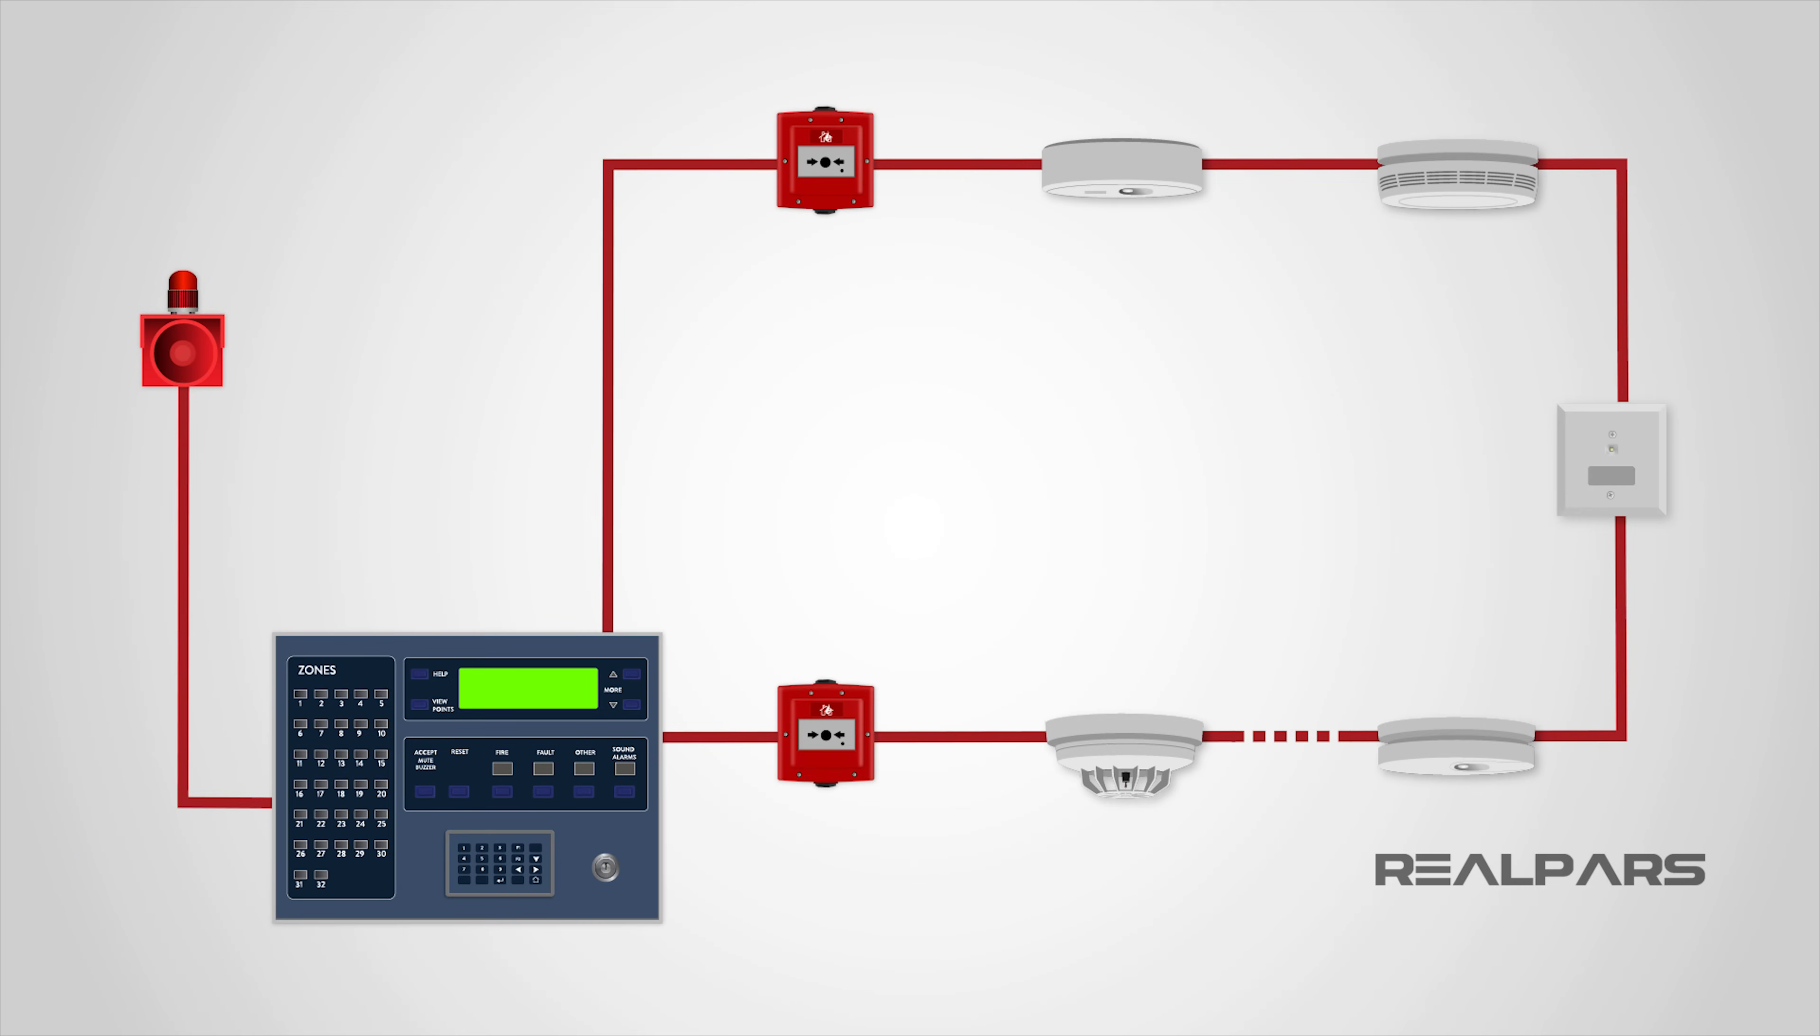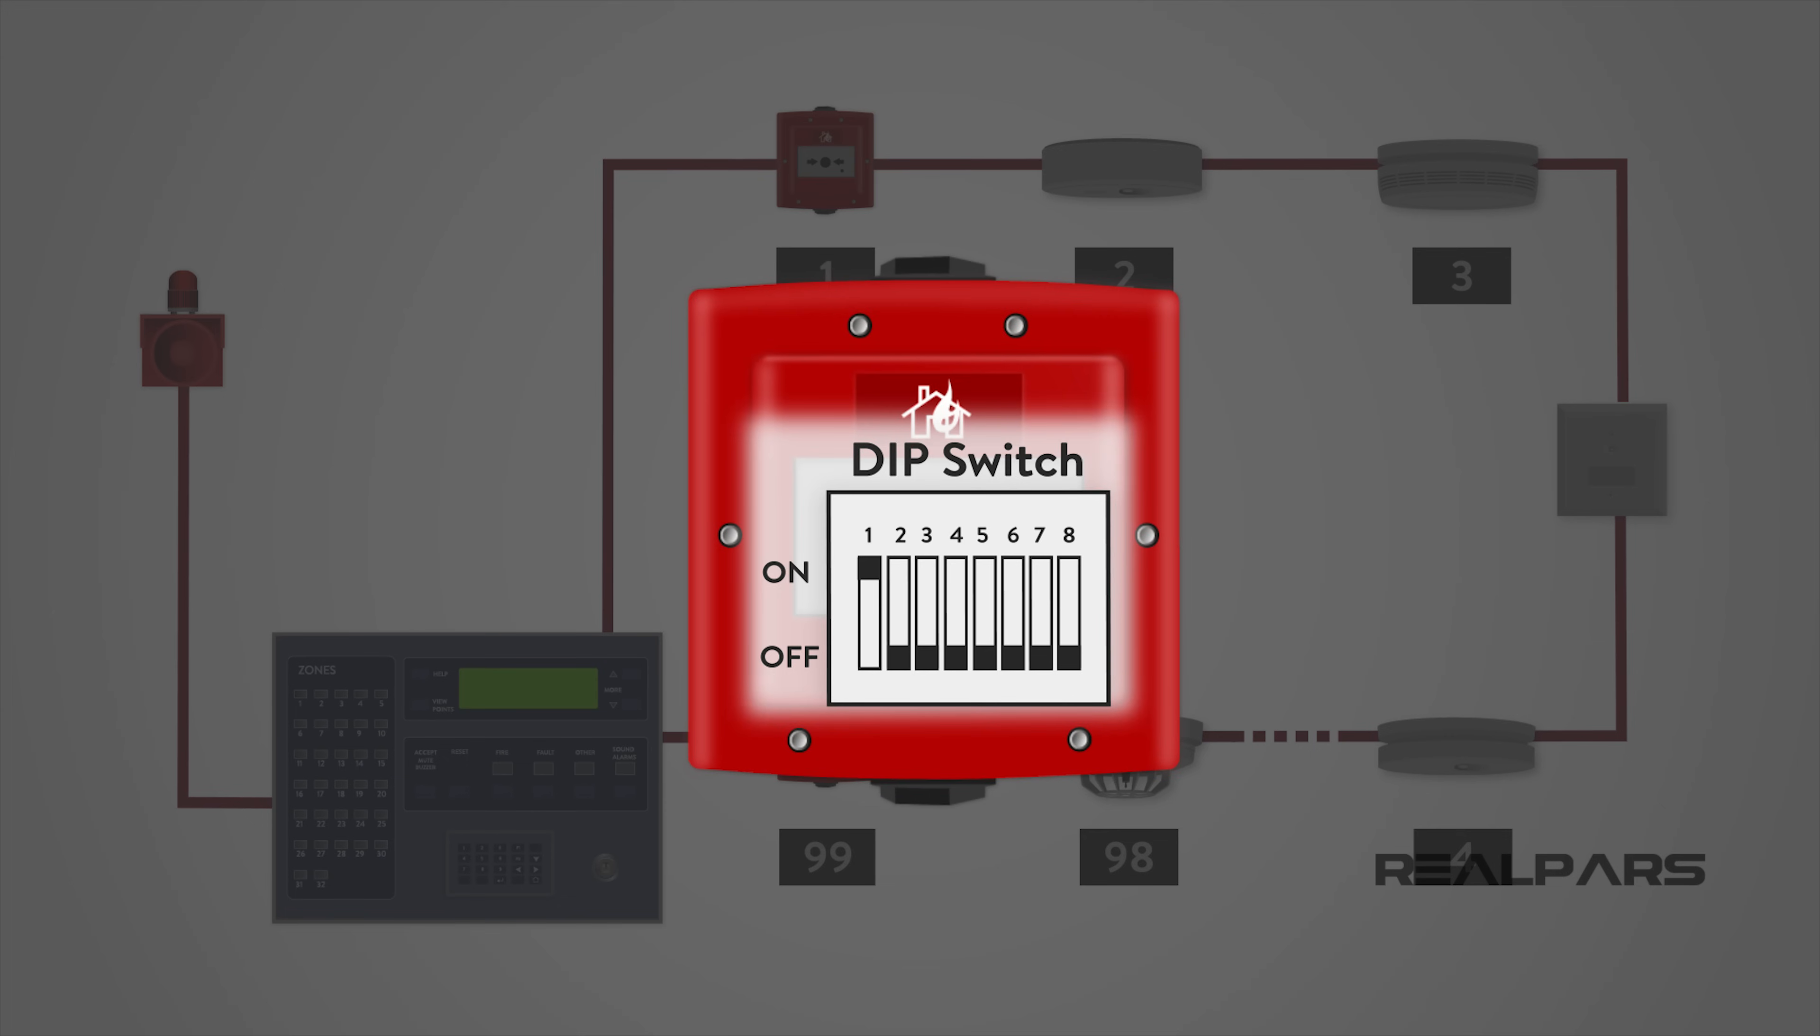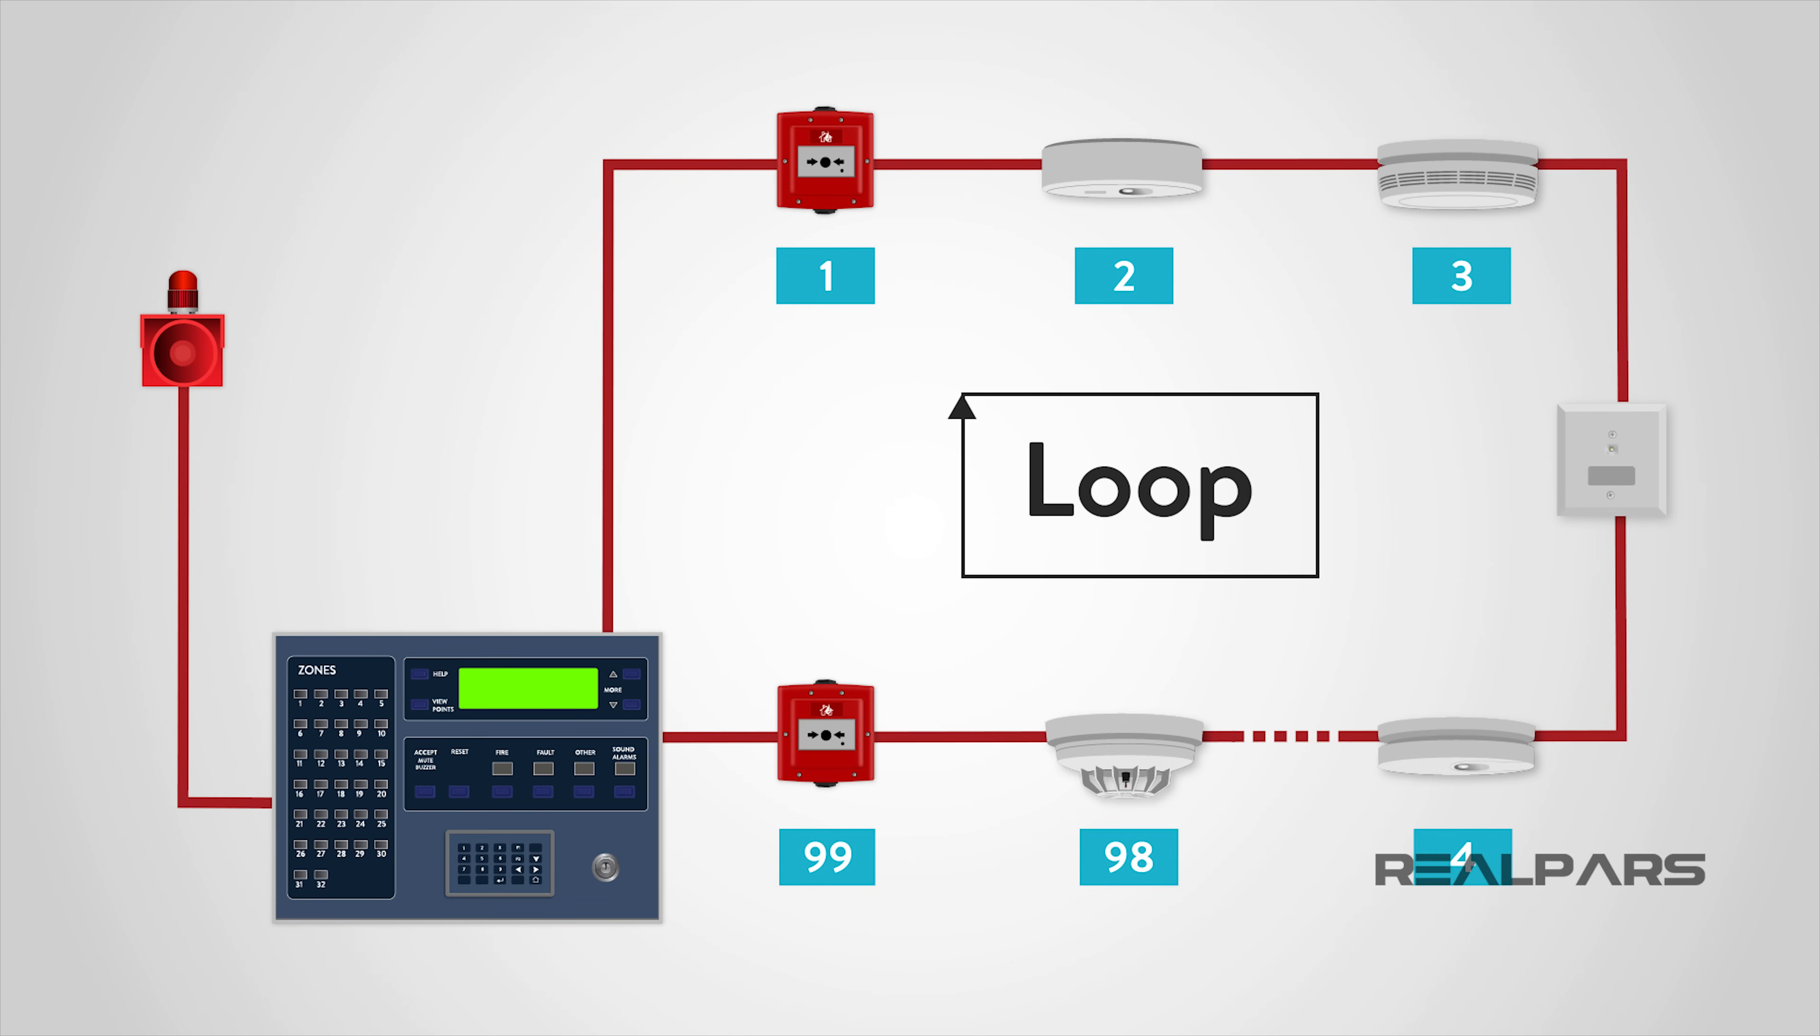The detection principle of an addressable system is the same as a conventional system, except that each detector is given a set address, usually by means of a dip switch, and the control panel can then determine exactly which detector, or call point, has initiated the alarm. The detection circuit is wired as a loop and up to 99 devices may be connected to each loop.